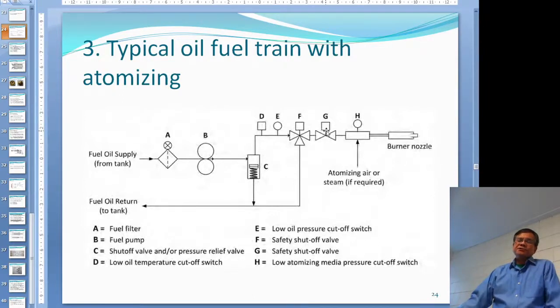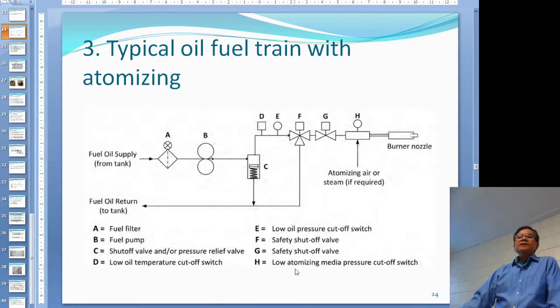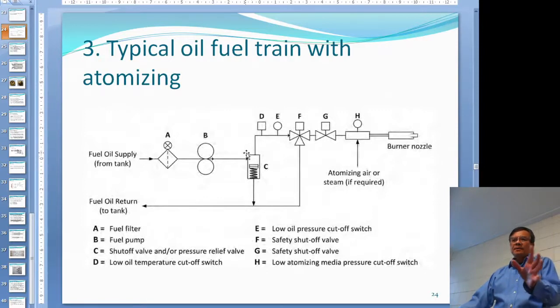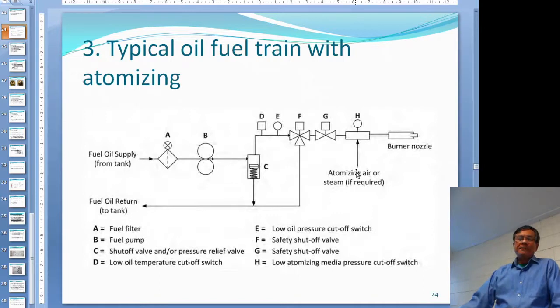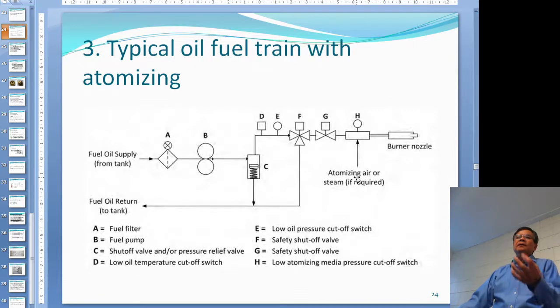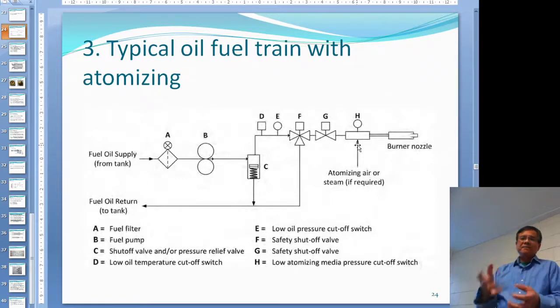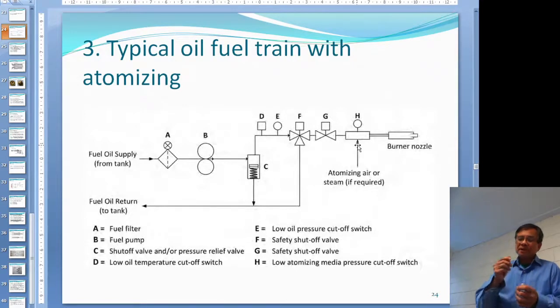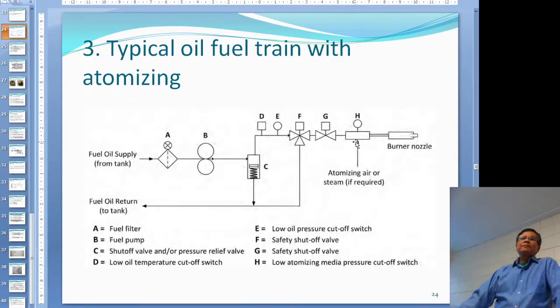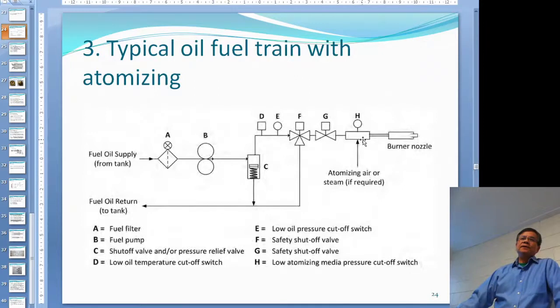G is just a solenoid valve. H is a low atomizing media pressure cutoff switch. This type of oil fuel train is for steam or air atomizing, not mechanical atomizing. If you don't have enough air pressure or steam pressure, you cannot properly atomize the oil — atomizing means breaking the oil into small droplets so you can burn efficiently. If you don't have enough atomizing steam or air, it sends a signal to the programmer and shuts it off. Inside the furnace there will be a burner.